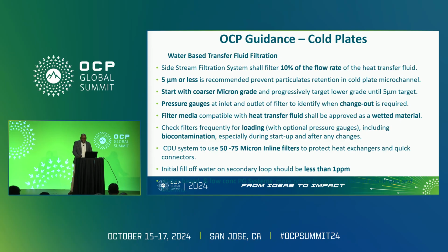Again, there's different advice given when it comes to micron grades that should be used, but the rule of thumb within filtration, if you've got, let's say, a primary filter, is that it should be 5 to 10 times more open than the filter downstream of it.